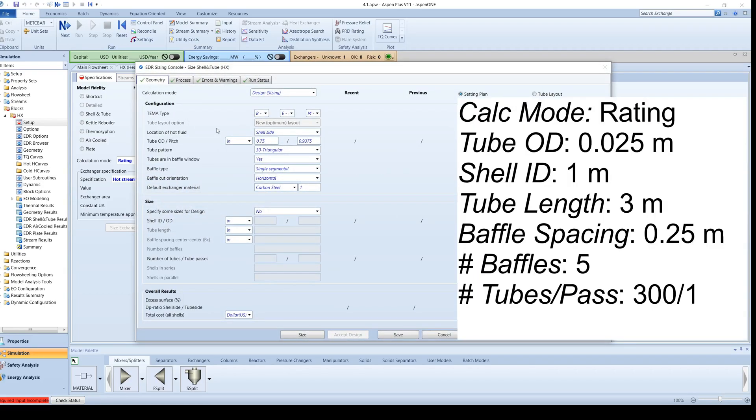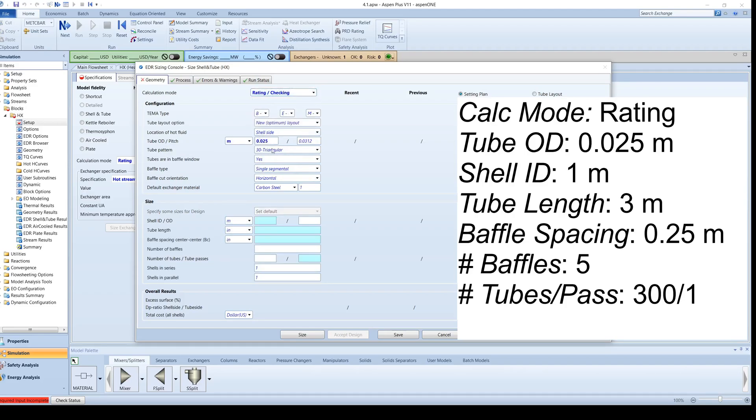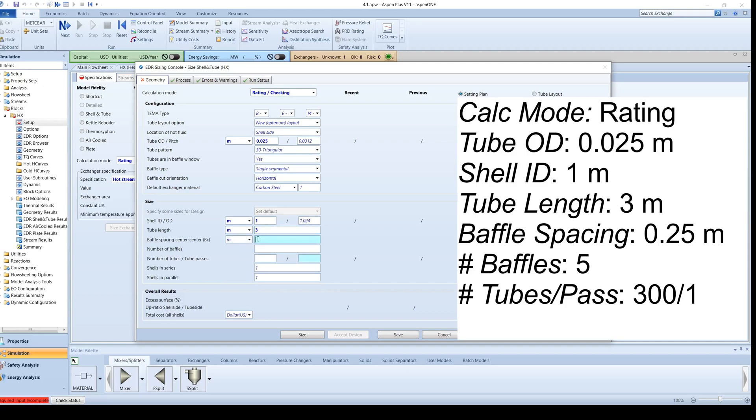Change the calculation mode again to Rating. For this simulation, specify the tube outer diameter as 0.025 meters, the shell inner diameter as 1 meter, the tube length as 3 meters, the baffle spacing as 0.25 meters, the number of baffles as 5, and the number of tubes per pass as 300.